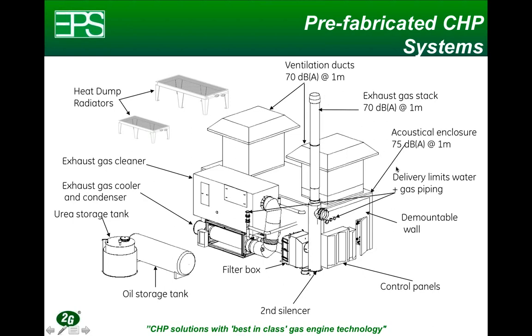We have an acoustical enclosure that is designed for a noise level of 75 dBA at 1 meter. Again, we have the connection points where we define our basic scope and from where the customer takes it. So we have the natural gas inlets, and we have the hot water connections where we deliver hot water to our customer. There is always a wall that can be removed for major maintenance, for major overhauls. If equipment needs to be removed from the enclosure, then it's easy to do with a removable wall. It shows here the control panels for a system like this. We have the exhaust silencer that is part of the stack. We have the exhaust heat recovery equipment.